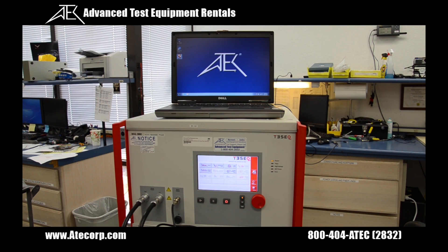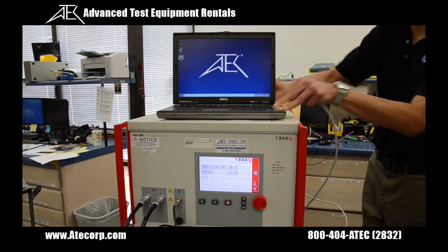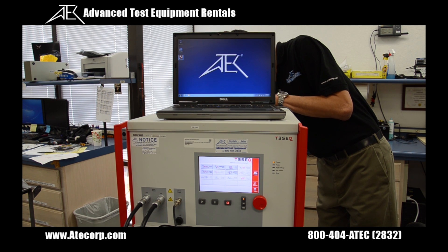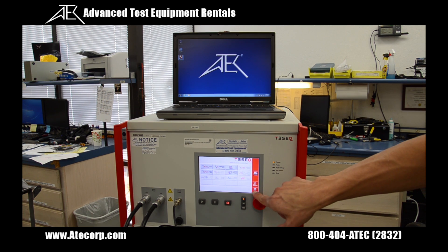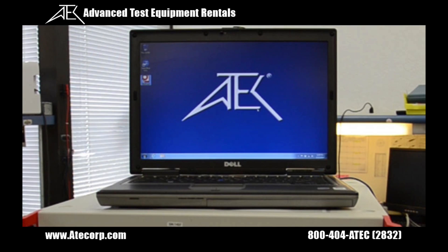Now we're going to show you how to run the NSG3060 from the WIN3000. The first step is to connect the ethernet cable from the laptop to the back of the mainframe. Then I'm going to set the NSG3060 in remote mode by pressing the remote icon. Finally, I'm going to double click the WIN3000 icon on the computer.